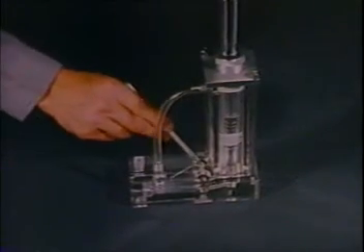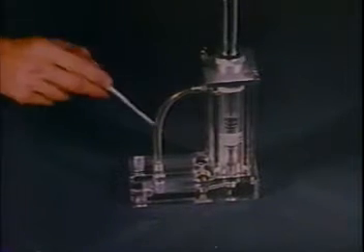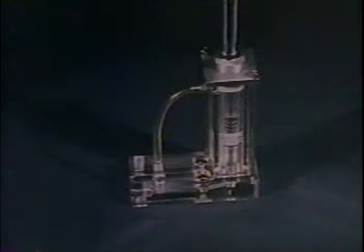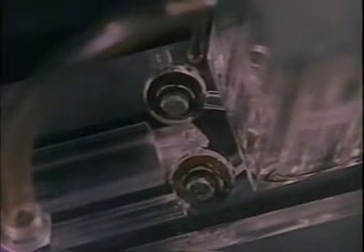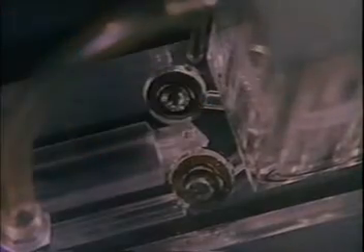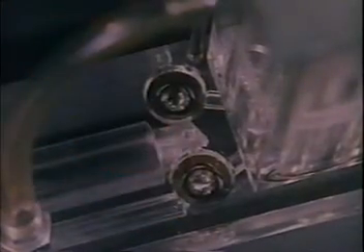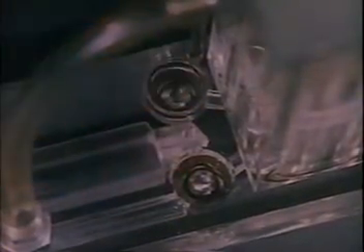The inlet ball valve on the rear side of the pump base and the discharge ball valve on the front side of the pump base are guided directly over the ball valve seat by a clover-shaped insert, which aids in rapid ball valve seating during pump reversals.